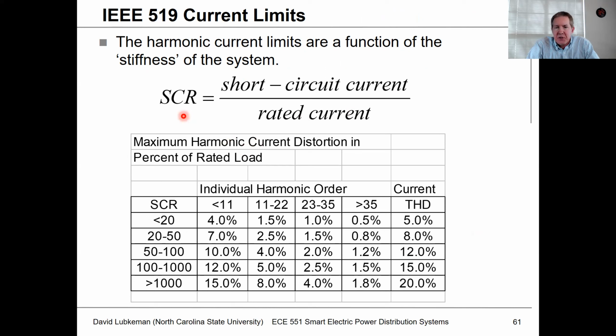And this is a function of the strength of the system. And so where we're injecting the harmonics, we look at what's called the stiffness factor, where this is the ratio of the short circuit current to the current being injected at the load side. And so the higher this value is, the less the system impedance, and the stiffer it is, the more resistant it is to causing harmonic overvoltages due to harmonic currents. And so if we have a really stiff system, then we could really tolerate really high harmonics. So below the 11th harmonic, we could have individual components up to 15% with the total harmonic distortion of 20. But if the system's weak, then these individual components can't be more than 4%. And then the total harmonic distortion is limited to 5%. And so this is a function of the strength of the system. The stronger the system, the more harmonics the system can withstand.